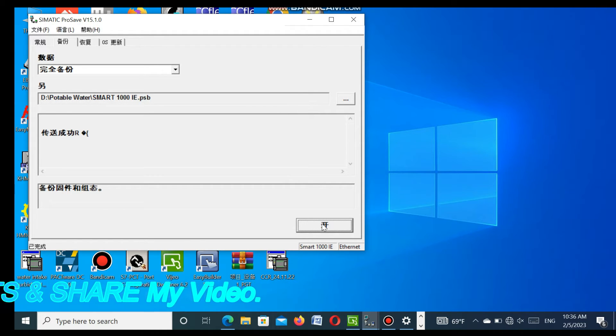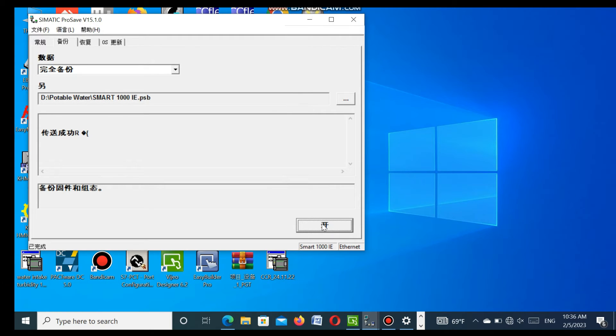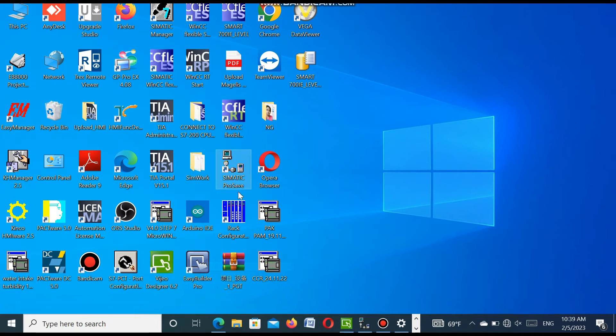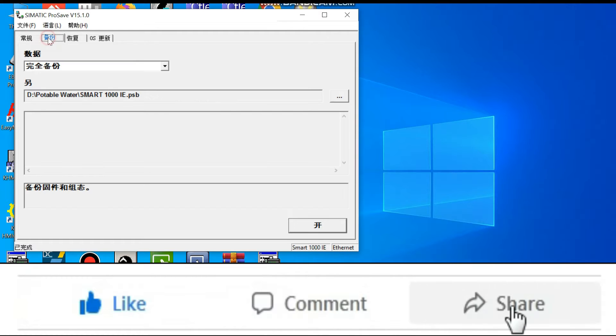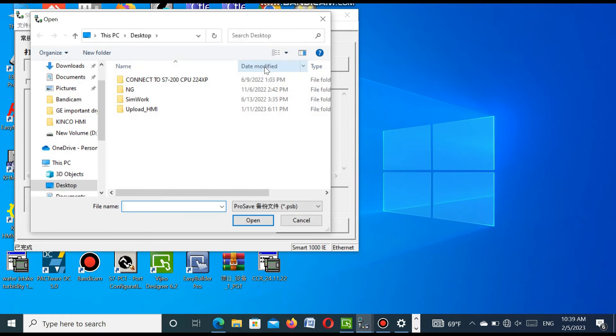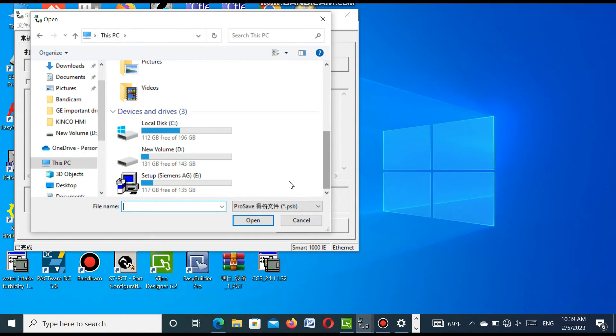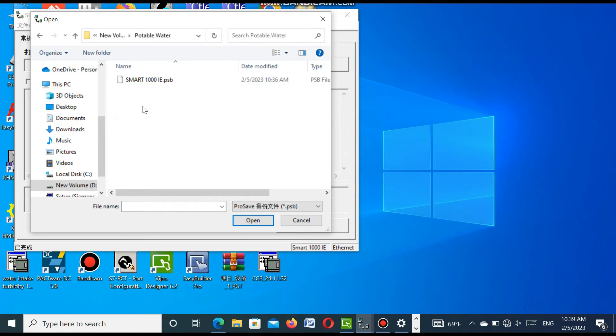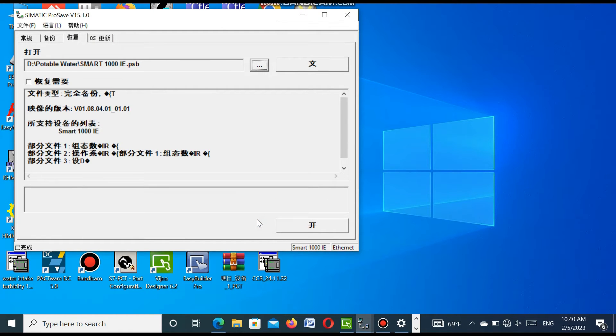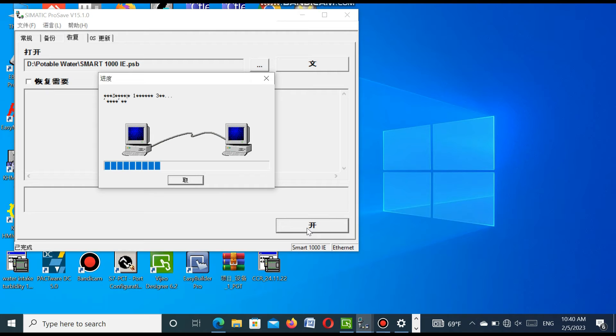Upload is completed and our program is already saved. Now, I will show how we can download this program to a new HMI. We again open the SIMATIC ProSave software. Then, go to the download option and select the program where we uploaded this program before — from this old HMI. We want to download this program to a new HMI. Open this program, select and press open. The program is open. You see, on the left side is download. Press the download button. You see, the communication is established between the HMI and the laptop, and the program is downloading step by step. All the firmware, project, and base files will be downloaded to the new SMI.